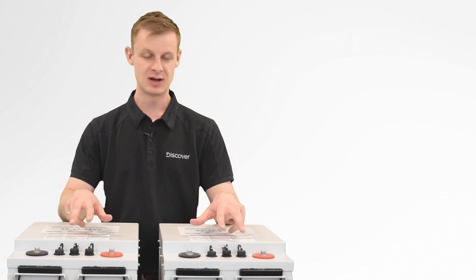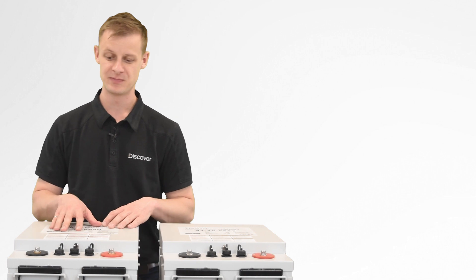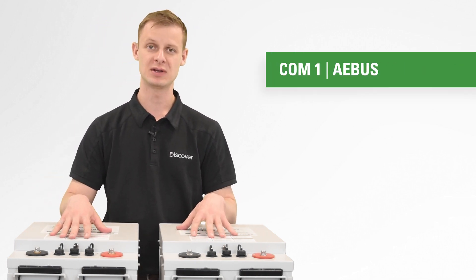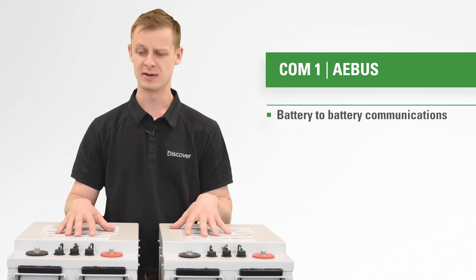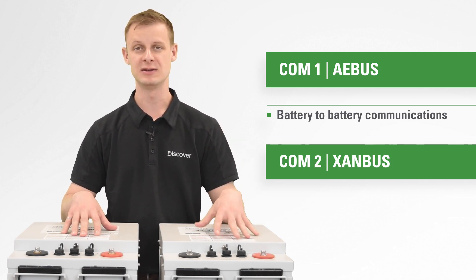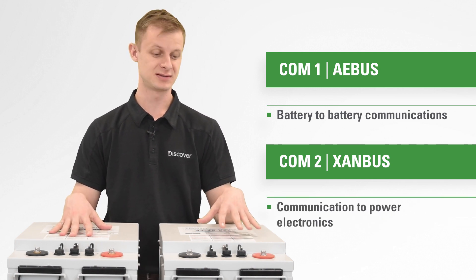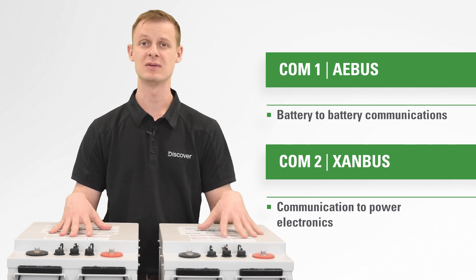You will notice that there are two COM ports in each battery, so there are two individual networks running on each battery. One is AE bus and that's battery-to-battery networking, so they're all aware of each other and coordinating what's going on. COM 2 is an external connection — in a network, you'll need one battery speaking to that external component. COM 2 in this case is XanBus, and you'd use that to connect to Schneider Electric's power electronics.